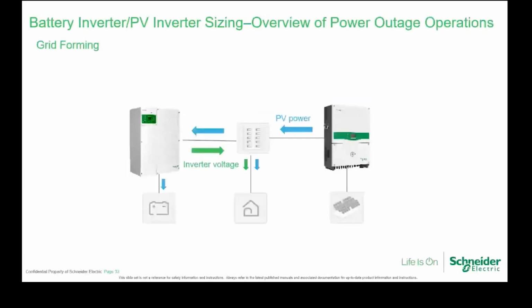Grid forming is when you have no grid or generator operational. And here, the inverter will provide the AC waveform for the PV inverter to synchronize with. And then that excess energy being generated can go into the loads or can go back into charging the batteries. Once the batteries are fully charged, it'll then do the frequency shift, which means the inverter will start derating itself, so that the power out of the PV inverter will match the load requirements.